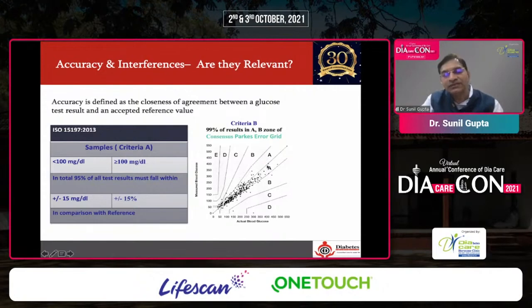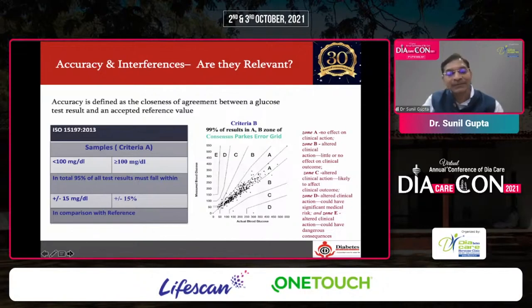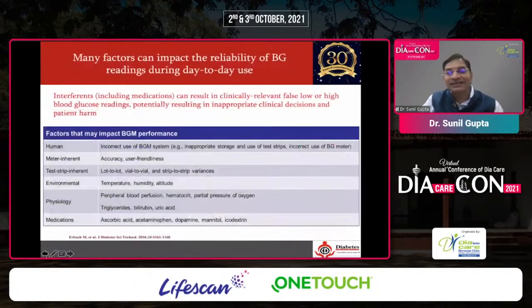Using the Parkes error grid, if results fall in zones A and B, it is acceptable. If a significant number of readings fall in zones C, D, or E, action needs to be taken regarding the glucometer's accuracy. Zones A and B have no effect on clinical action, but zones C and D would require addressing the accuracy of the glucometer.